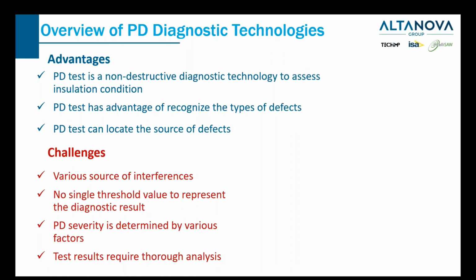Is it a surface discharge, or is it just a corona discharge of a needle electrode, or is it a void discharge inside of the insulation? So PD test can recognize the type of defects. And another advantage of PD test is it can locate the source of defects.